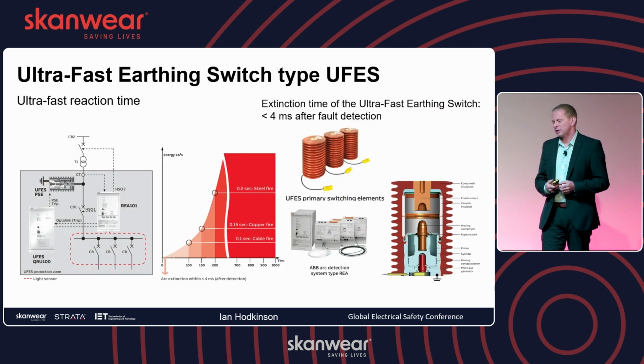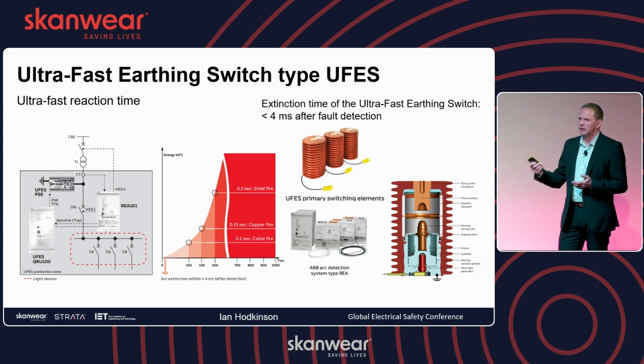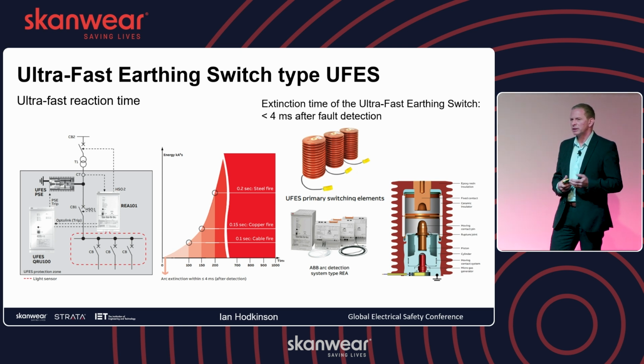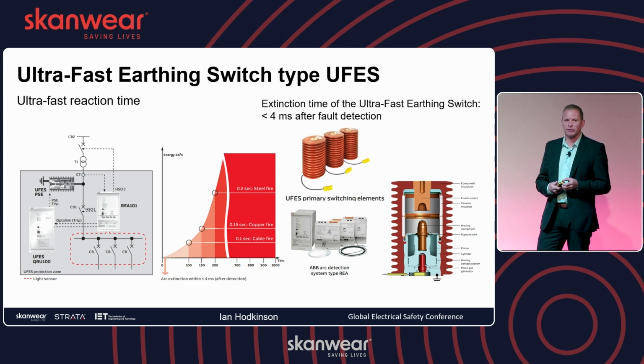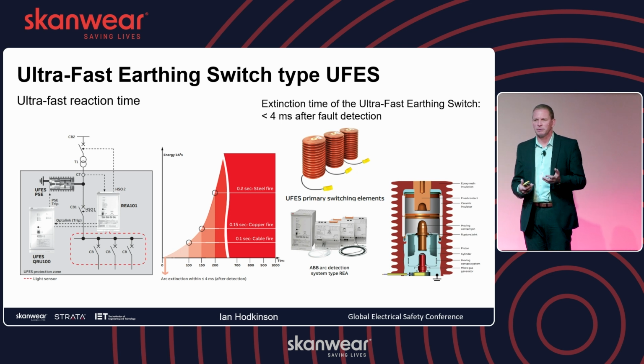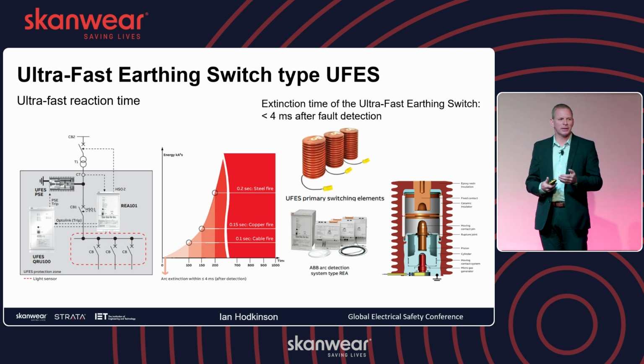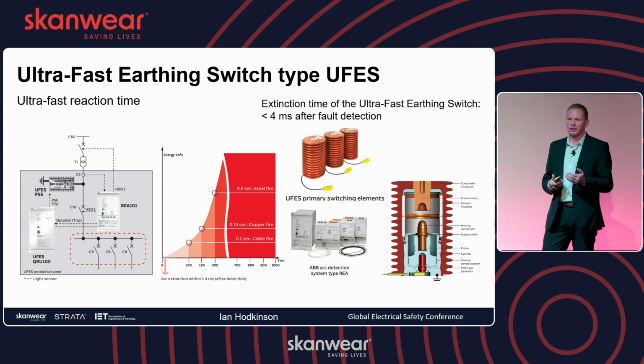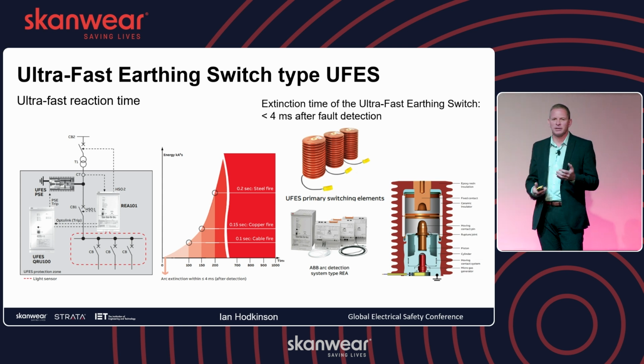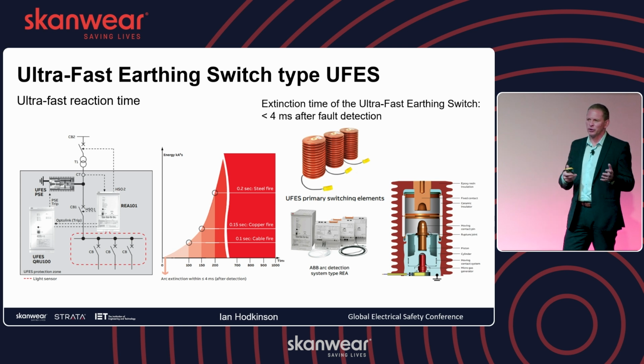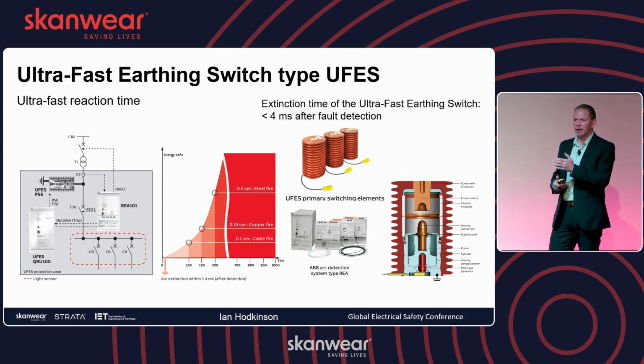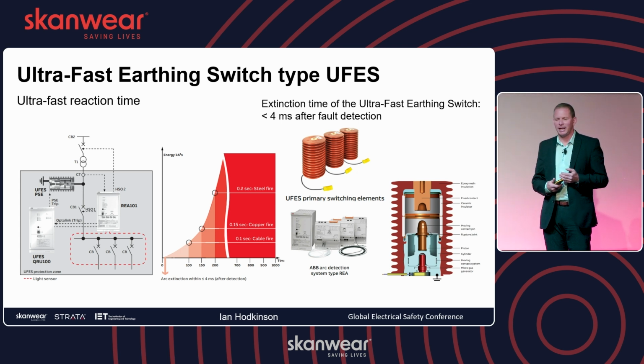Some of the other devices and methods we're talking about, as Mikko touched on, is quenching. This is sort of quenching, but it's maybe more redirecting the arc flash, which is our UFES, the ultra-fast earthing switch. So we normally use this in combination with an arc protection or arc detection system. The arc detection system can operate and pick up in 1 or 2 milliseconds, and it's normally the breaker that takes the additional time, because we're usually tripping a breaker, which for most medium voltage breakers is 40, 50 milliseconds, or low voltage 60, 70 milliseconds. So that's your total clearance time. This enables you, if you've got a very high incident energy level on your board, to get full clearance of your arc in 4 milliseconds.